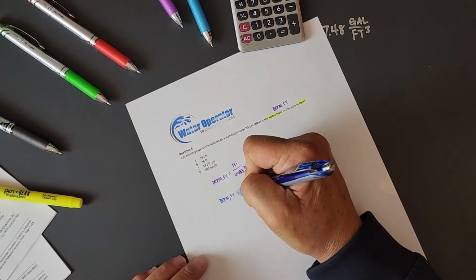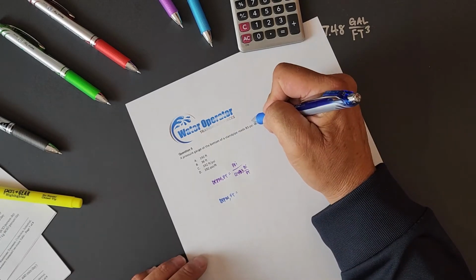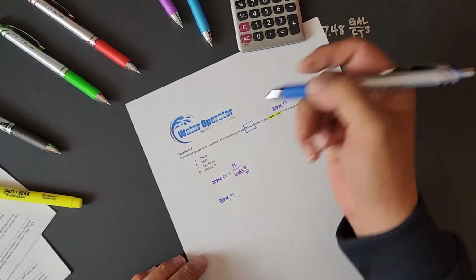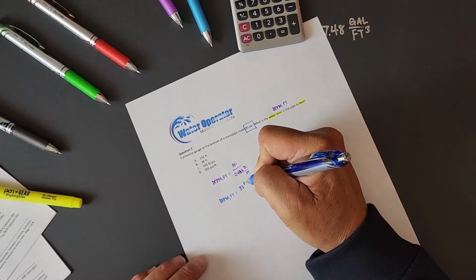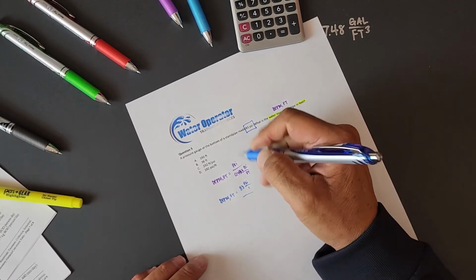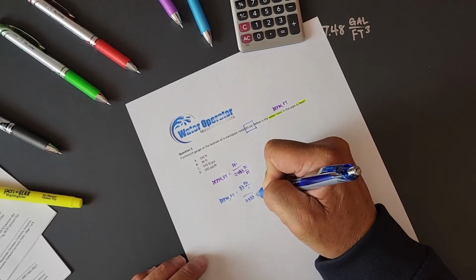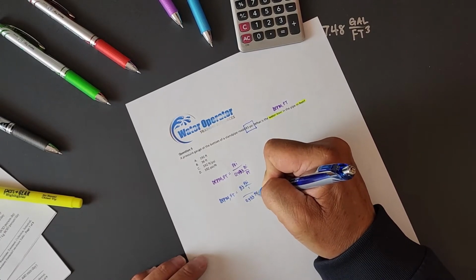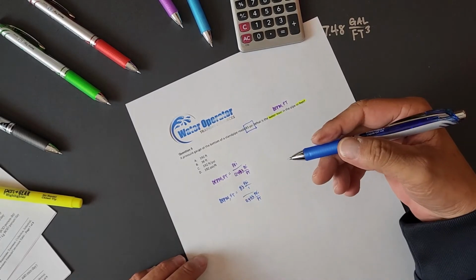Depth in feet equals the pressure gauge at the bottom of the standpipe, which reads 83 psi, over 1, times 0.433 psi per foot. I'm just being a little extra careful.